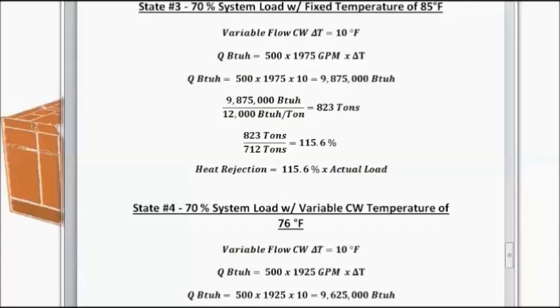And we'll also see a change in percent heat rejection. And this is due to a more efficient operation of the variable speed chiller that we are simulating. It has little to do, though, with the reduced flow. 823 tons now is the calculated heat rejection load. And if we compare that to the actual cooling load of 712 tons, the heat rejection is about 115.6% of the actual load.